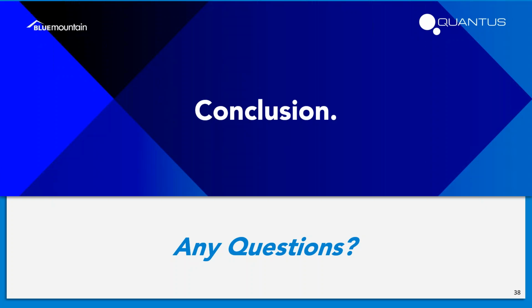And then one other question we had that came in, and we're going to have to wrap up because we're hitting time. Regarding service intervals for calibrating instruments, you talked about service intervals of 3, 6, and 12 months. Is it always necessary to perform calibrations at those intervals, or can you choose an interval somewhere in between, for example, every 9 months?